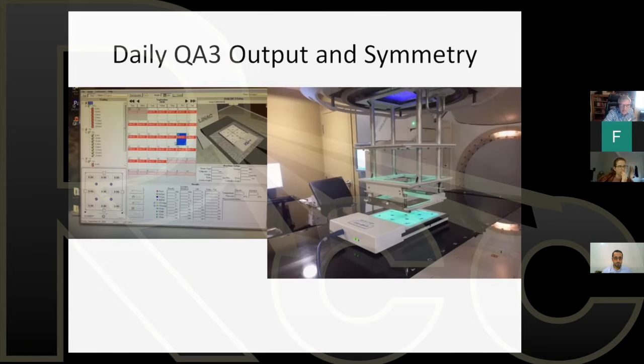It's a daily check, and you can see here that the physicist has established protocols for each machine. There's 3 linear accelerators in my clinic. So there's different energies for all the 3 linear accelerators, and it can be tracked on a daily, weekly, monthly, even yearly plot. So the physicist can check this every day and see that the test has been performed. Does it meet specification, and how is that trending?